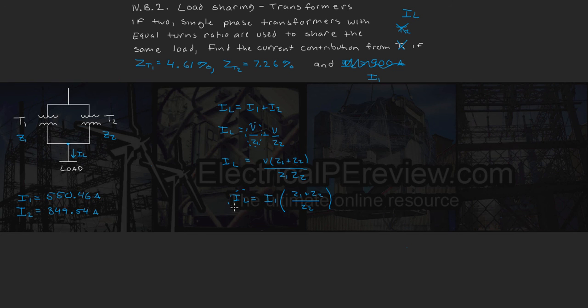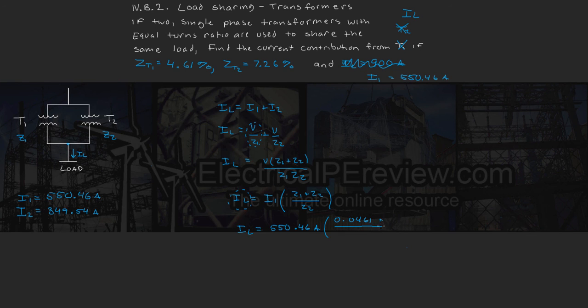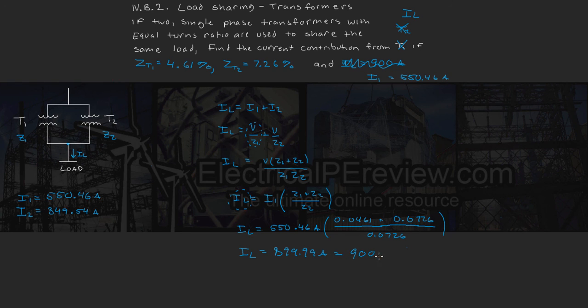Since we're searching for the load current, we plug in our terms. We know I1 equals 550.46 amps. Multiplying that by the sum of our impedances — 0.0461 plus 0.0726 — over Z2 gives us IL equals 899.99 amps, which equals our load current of 900 amps.